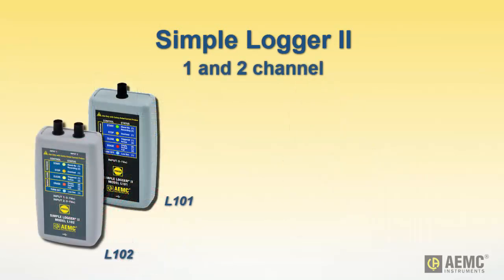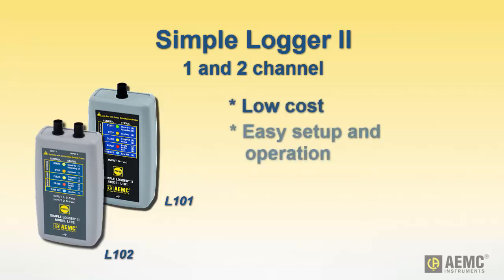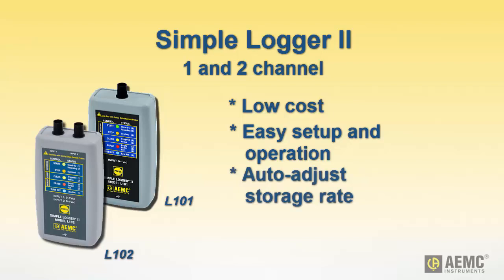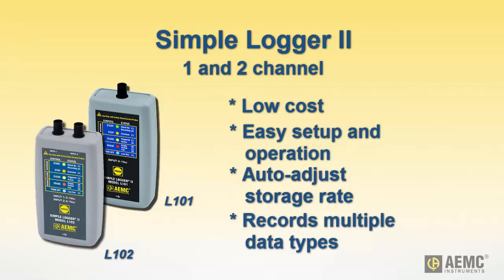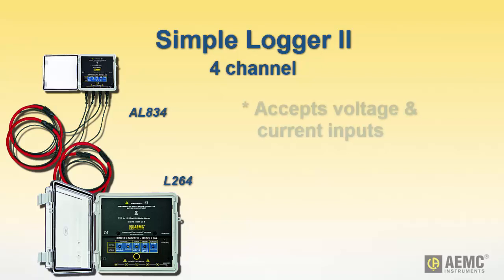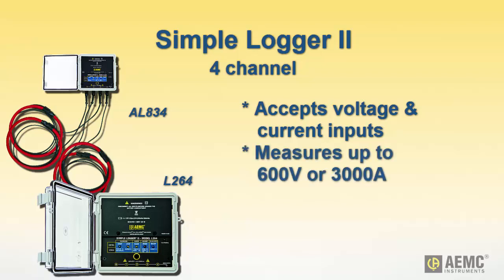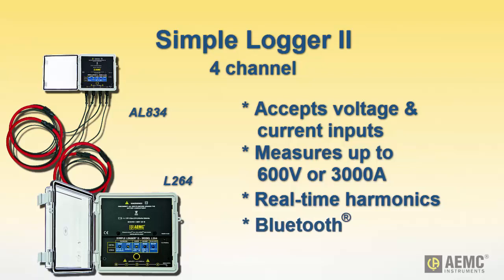These instruments are low-cost, battery-operated data loggers that require minimal user setup. They can automatically adjust their storage rate to optimize the recording of data, including temperature, events, thermistor, 4–20 mA, AC and DC voltage, and AC and DC current. The 4-channel models are used primarily to measure AC, and accept voltage, current probe, and current sensor inputs. Voltage inputs are directly measured up to 600 volts, and current inputs up to 3,000 amps. Two- and 4-channel models use captive AmpFlex current sensors. Harmonic measurements are available in real time, and for some models, Bluetooth communication provides data transfer from the instrument to a computer.